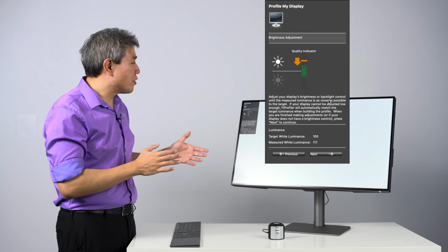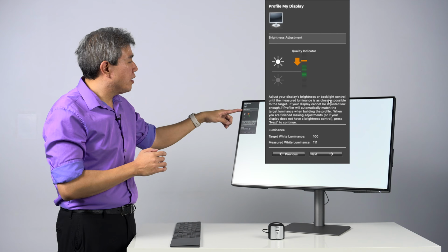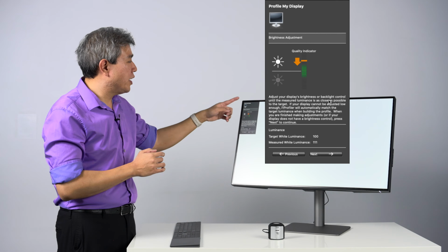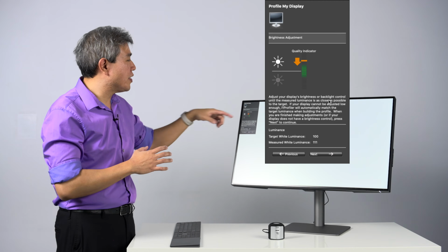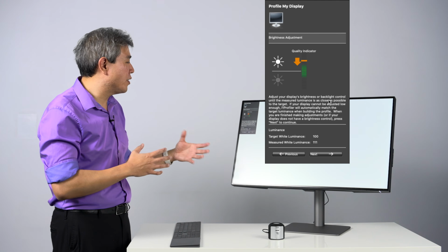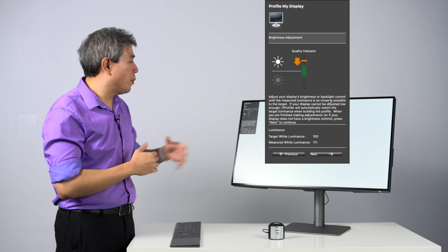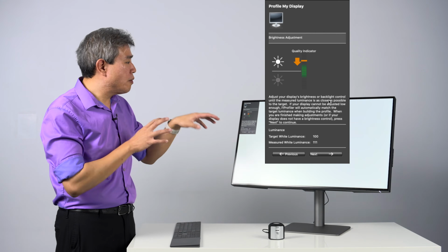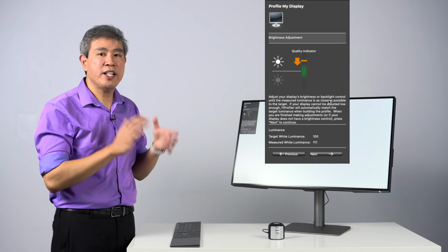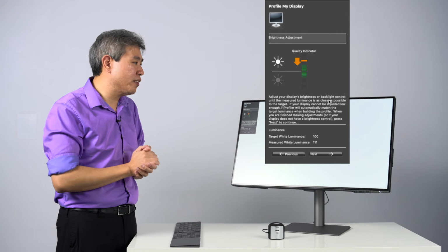Now that we are at this screen, this is telling me the brightness adjustment or the quality indicator. The quality indicator in this case is really just the brightness range. So right now, the target that I want is 100 candela, whereas measuring right now in the center of the screen is 111. It's about 10 candelas too high.